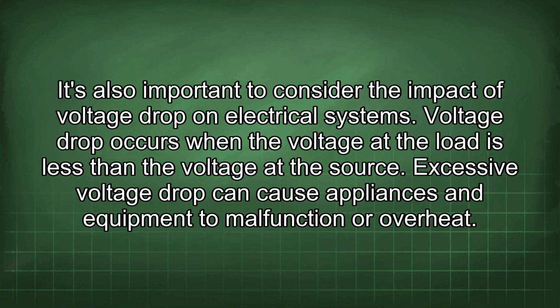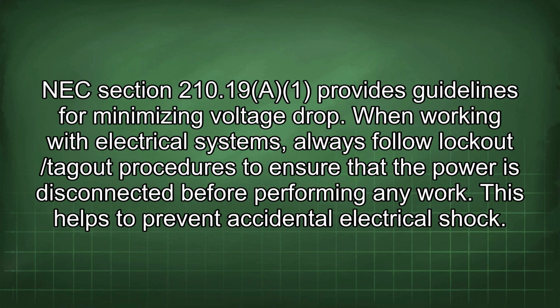It's also important to consider the impact of voltage drop on electrical systems. Voltage drop occurs when the voltage at the load is less than the voltage at the source. Excessive voltage drop can cause appliances and equipment to malfunction or overheat. NEC Section 210.19 provides guidelines for minimizing voltage drop.